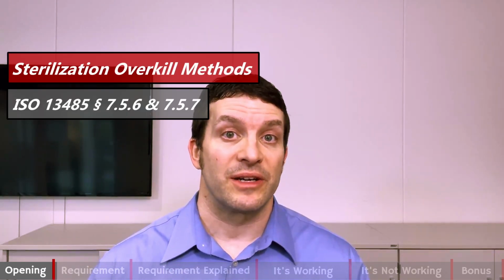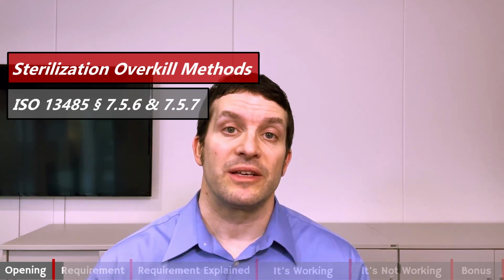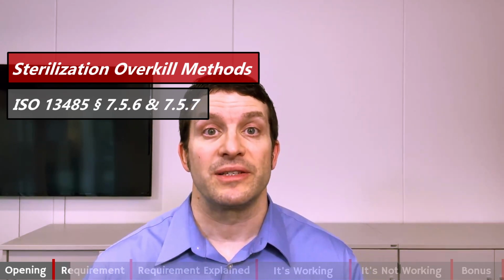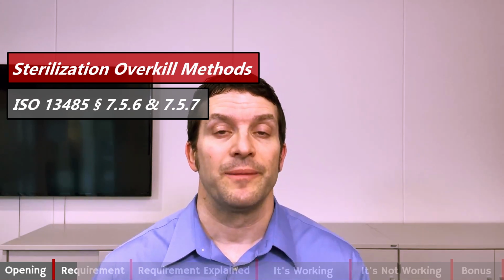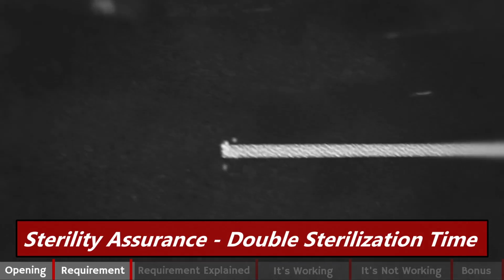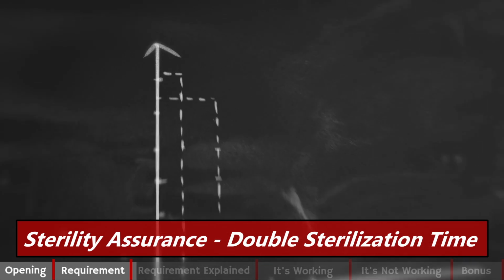Our topic, sterilization overkill methods, is covered by 13485 section 7.5.6 and 7.5.7. There is a corresponding ISO standard, 11135-1, Sterilization of Healthcare Products, Ethylene Oxide, Part 1. Requirements for the development, validation, and control of routine sterilization processes for medical devices. Overkill sterilization in 5 words: Sterility assurance, double sterilization time.